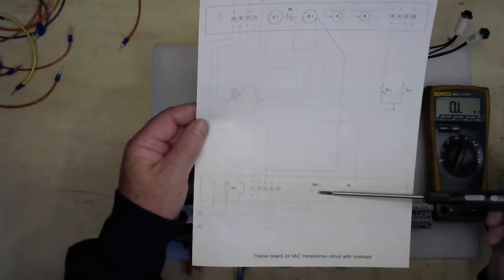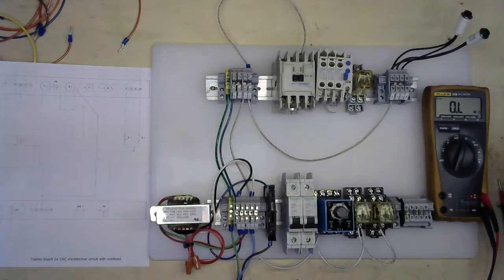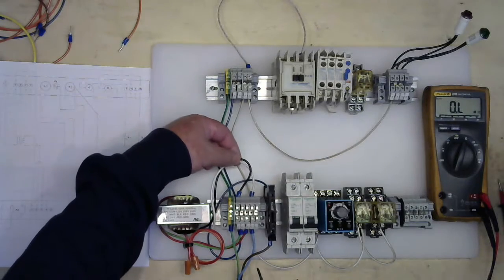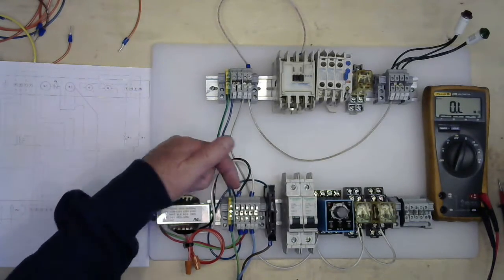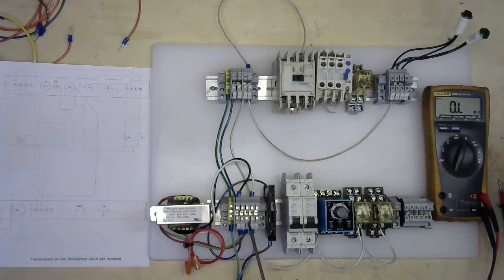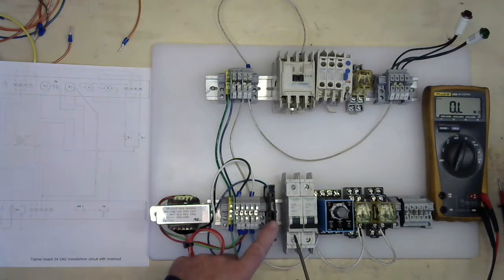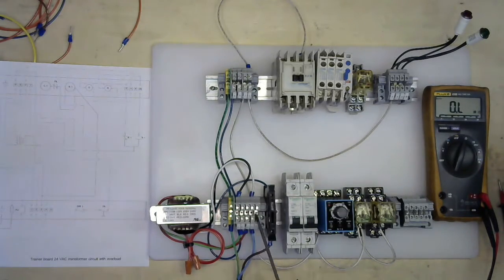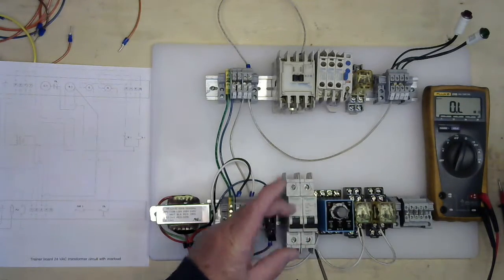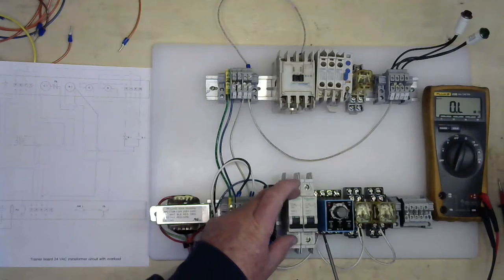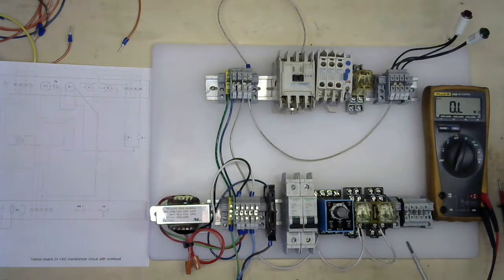We have a 24 volt time delay. We're using a switch. We're going to have circuit breakers as a switch, and then our fuse. Looking here at the training board, we have a 120 volt primary, 24 volt secondary transformer. I have my 120 volt primary already connected to the terminal blocks. I have the secondary side on terminals 2 and 3 already connected to the terminal block. We have our incoming power coming in through our fuse, out of the fuse, powering at the terminal block. We're using circuit breakers and acting as switches. That way they fed onto the DIN rail faster and easier.